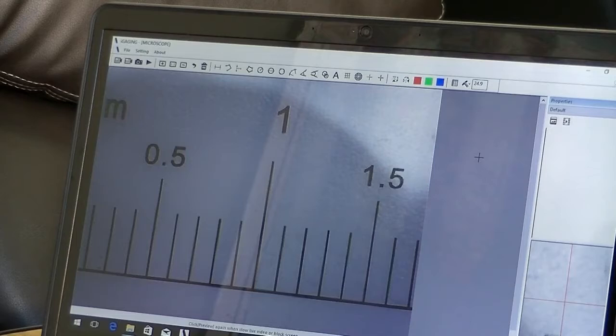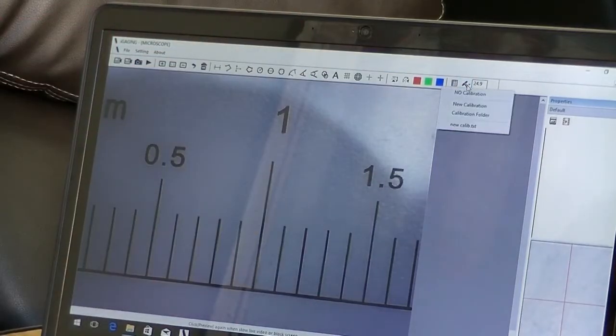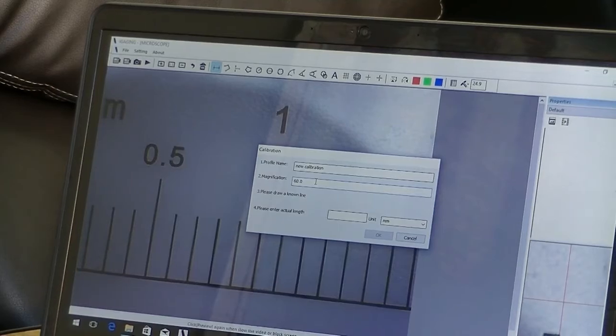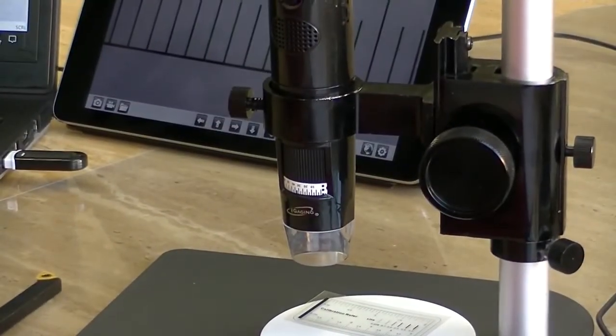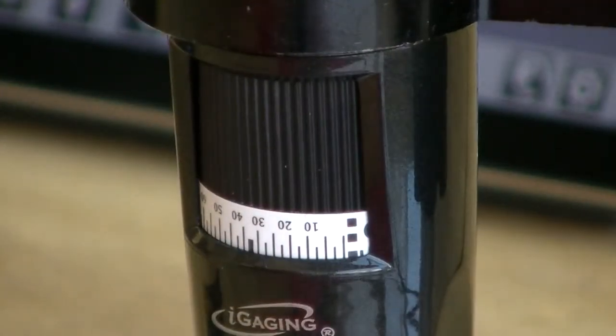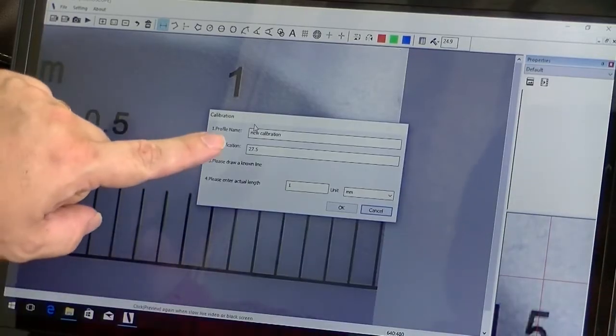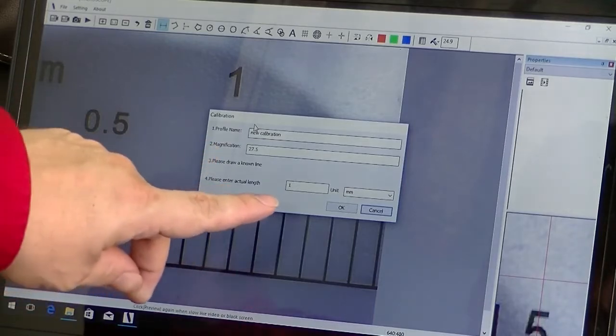Now one of the cool things you can do with this microscope is to actually measure microscopic devices. So let me show you how to do that. First thing you want to do is calibrate the instrument. So I go over here to the calibration, and I click New Calibration. Okay. And let's just call it New Calibration. Alright, and now it says the magnification is 60. Well, it's not 60 on my microscope. So if I look down here and I zoom into the microscope, you can see that it's actually about 27.5.